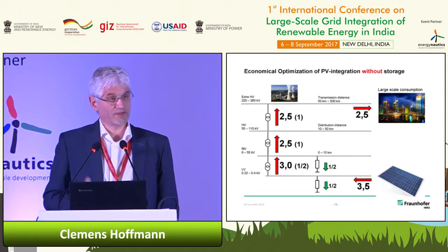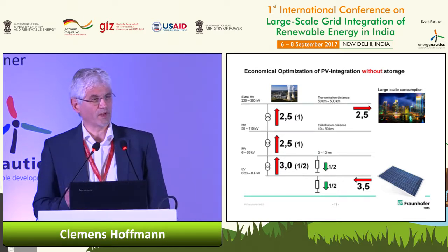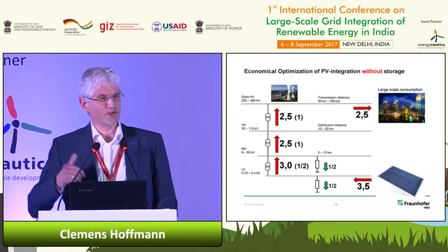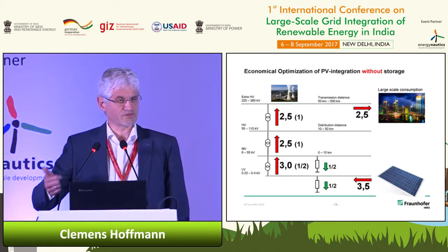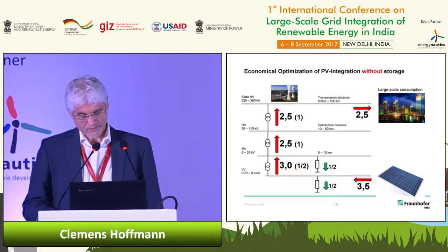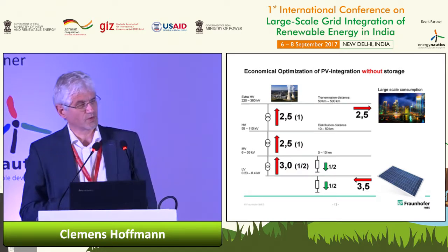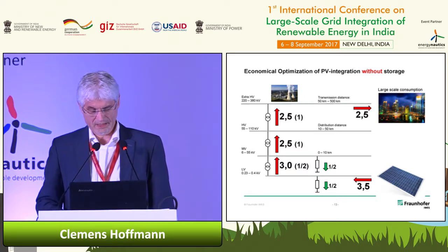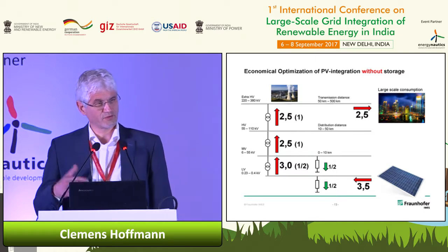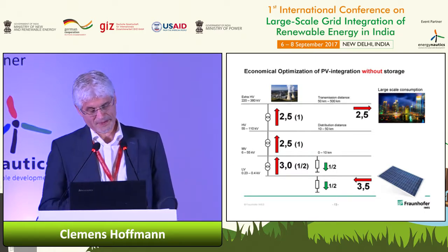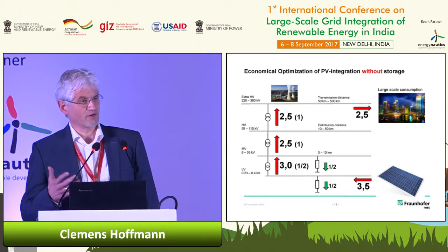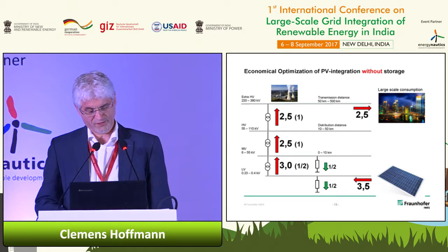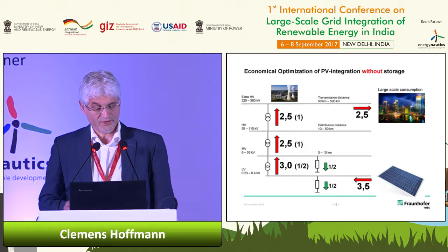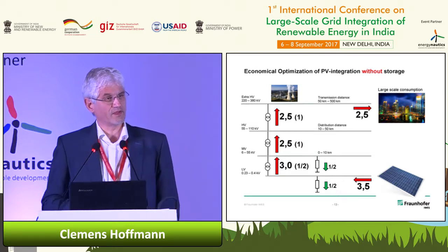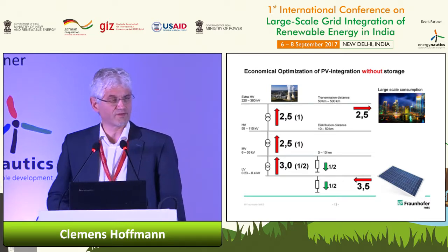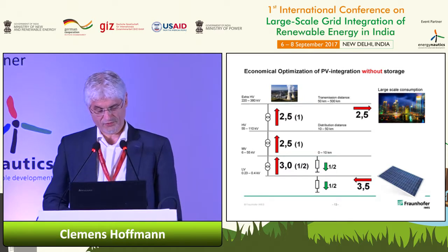But then 3, the power of 3, has to go through the first transformer, meaning we have to reinforce everything there 3 times - the transformer, the lines. What we can do is again consume the other 1/2 here, and there's a rest of 2.5 that we still have to pump up, meaning reinforcing the medium voltage transformer. This is again transported up, and at the extra-high voltage level, we have to reinforce by a factor of 2.5.